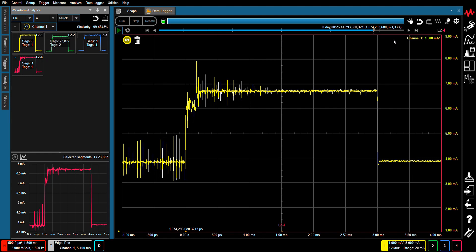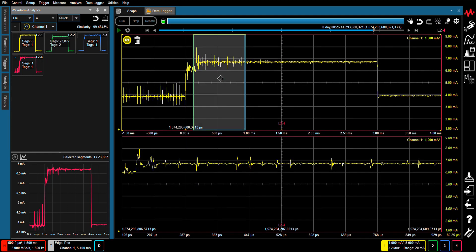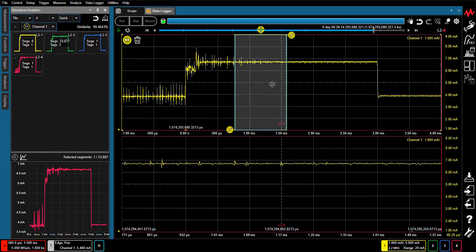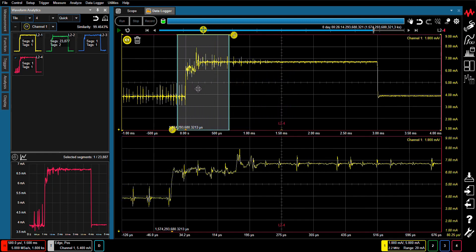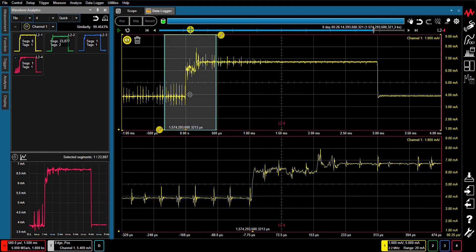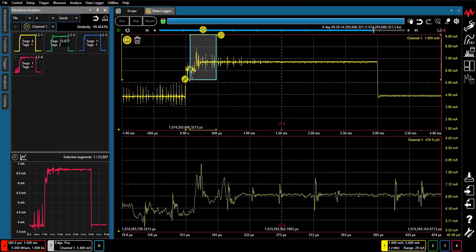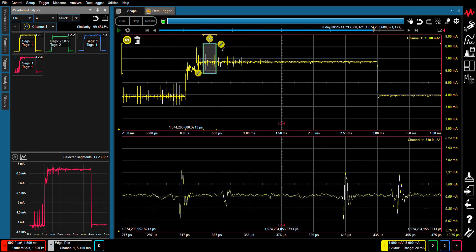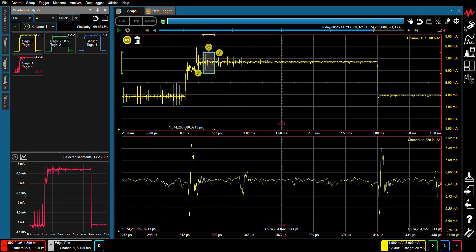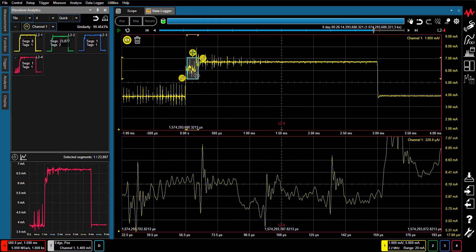The Anywhere Zoom function enables you to enlarge a specific area you want to see while still providing a macro view of the entire waveform. You can see the details of waveforms very clearly after zooming because the CX3300 has a 14 to 16-bit high-resolution ADC.